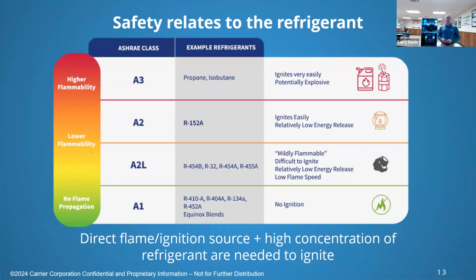R454B falls in this A2L category. In fact, they had to split the A2 category because it was so low in flammability that they had to make a different category for it. One way it's been described, and y'all may have heard it at dealer meetings, is if you had a piece of charcoal with no fluid and a match, trying to light that charcoal, that's about the flammability level of the 454B refrigerant. It's very low, but it is above the A1 no flame propagation line. Because of that, we have some things we have to do to deal with leaks and so forth. In my opinion, there's more concern about the oil in the system igniting than the refrigerant itself, but that's my theory as of now.